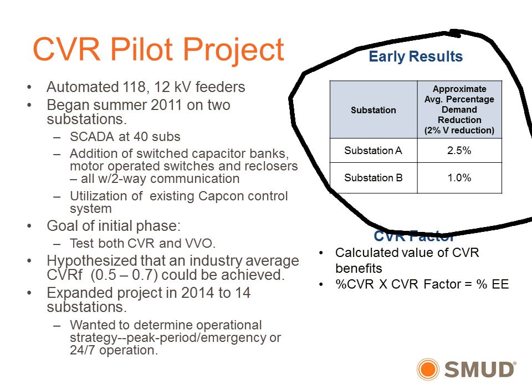You can see that on one substation we reduced voltage by 2% and saved about 2.5% in energy. On the other substation we reduced energy use by about 1%. I'd say that 1% is really within the bandwidth of error, so we believe we saved energy, but we can't say that for sure.